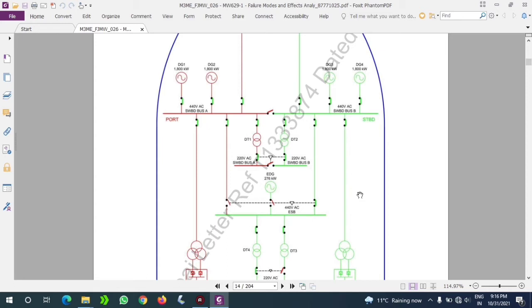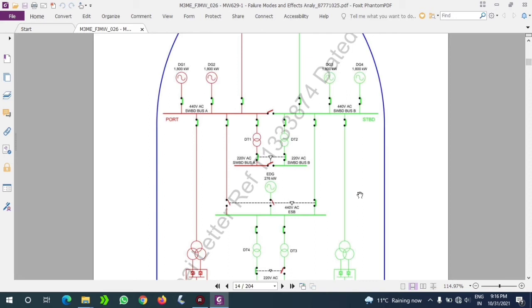As I said, as per the SOLAS requirement, if both bus bars failed, our emergency generator should start and come on load within 45 seconds, and it should start giving power to the emergency bus bar. This is a very important point - you should always remember that emergency generator should start and come on load within 45 seconds and it should give power to its consumers.